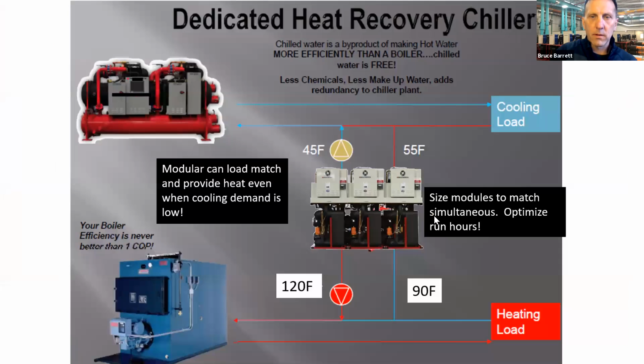All right, so I would assume it's this slide. Yep. Okay, so we've got a boiler on the bottom left, a chiller plant on the top left, and in between is our heat recovery chiller. It's dedicated heat recovery. Its sole purpose is to supplement hot water and cold water. So a side stream series, we're taking water, returning back to that chiller, extracting the heat, adding heat of compression, and cooling the water before it gets back to our main chiller plant. The heat we've extracted, we're adding to the hot water loop. So this is the basic dedicated heat recovery chiller schematic.